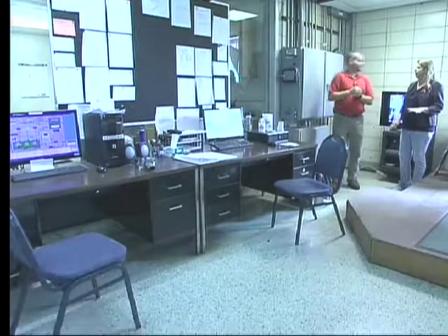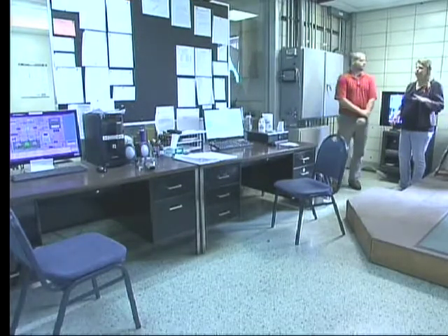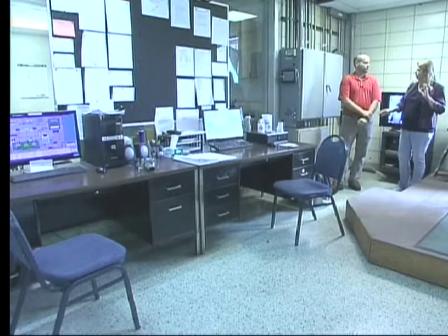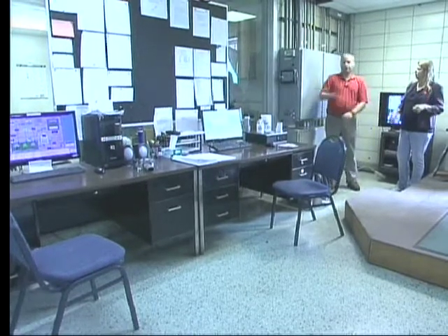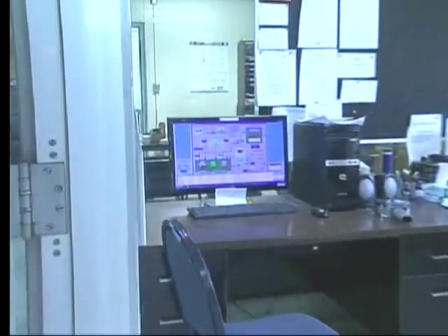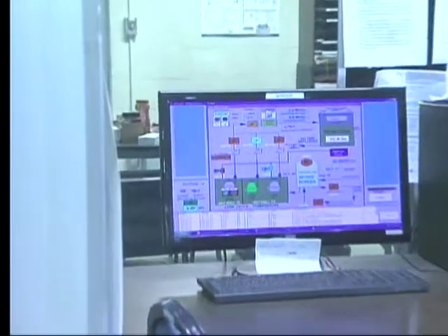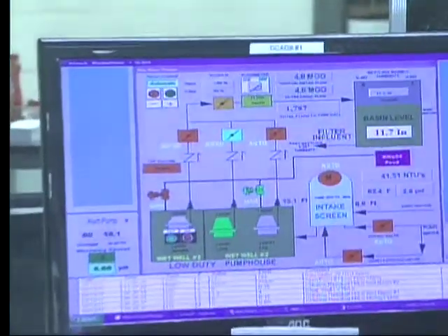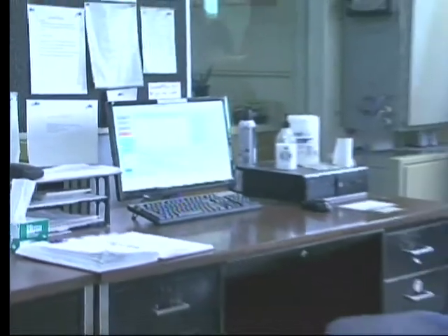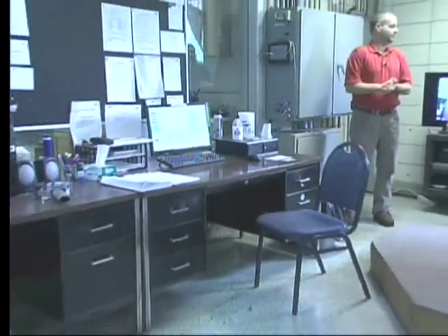What about maintenance things? So it will tell you if a pump is faulty, or if it's shut down, or if it needs a new part? Yes, there's numerous controls in there for measures to know if a pump fails, hours of operations for preventive maintenance, counting the hours of a pump running. If there's a failure of a Public Works pump in the system, we'll get an alarm for that as well. But it monitors every single item in this facility.